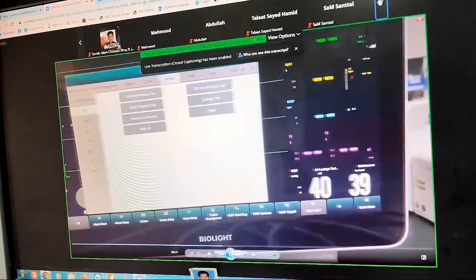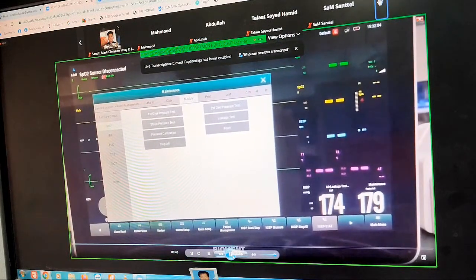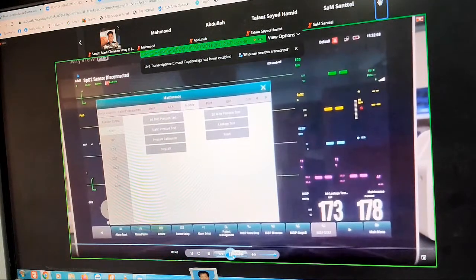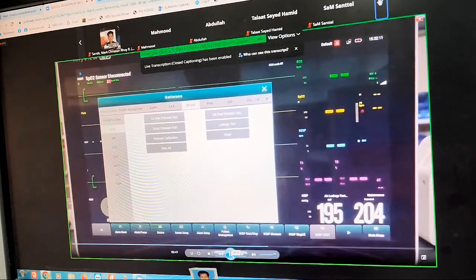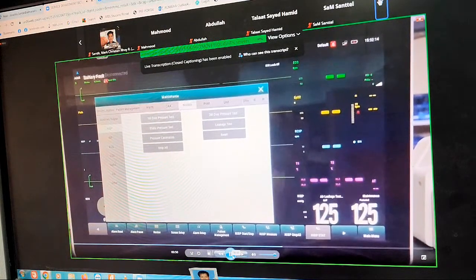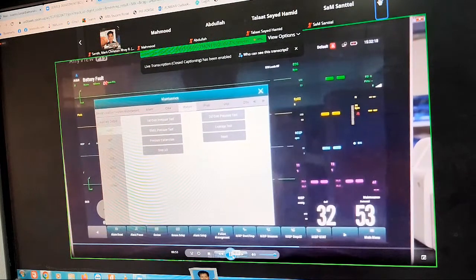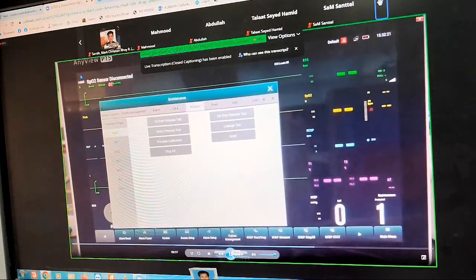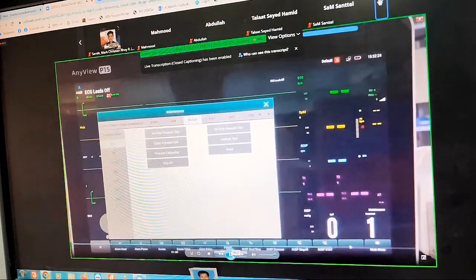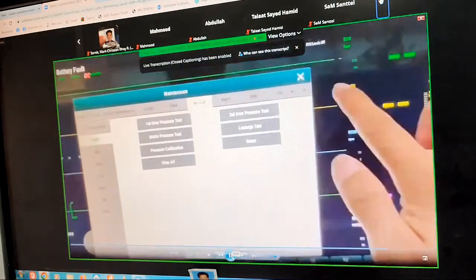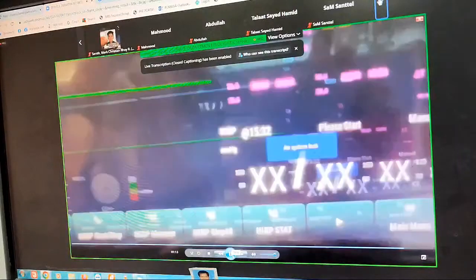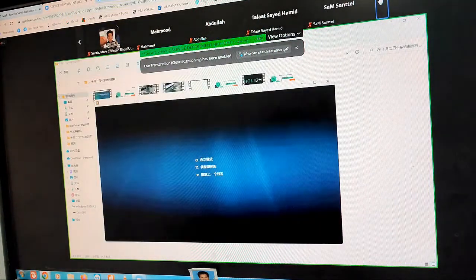You can hear some air sound here. So you can see an alarm here. It's an NIBP air leakage alarm. It means we have to calibrate the leakage. And we'll show you the next video, about the leakage test.